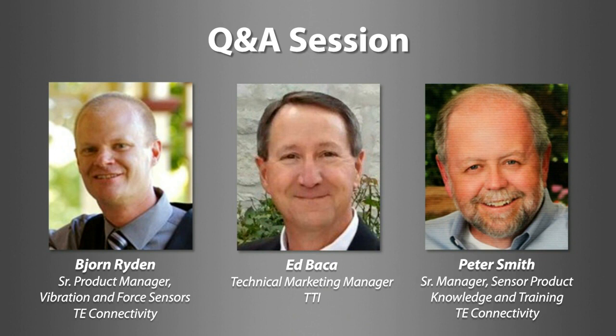And finally, drift. Piezoelectric crystals themselves are inherently much more stable than a MEMS device. A MEMS device is always under stress and strain. It drifts over time. We have MEMS devices in our portfolio. We have piezoresistive, and we also have DC MEMS devices in our own portfolio. We just don't target condition monitoring with that technology. And the reason is, as I've mentioned, the wide bandwidth, the dynamic range, and the long-term stability. And hence why we choose the PE technology.